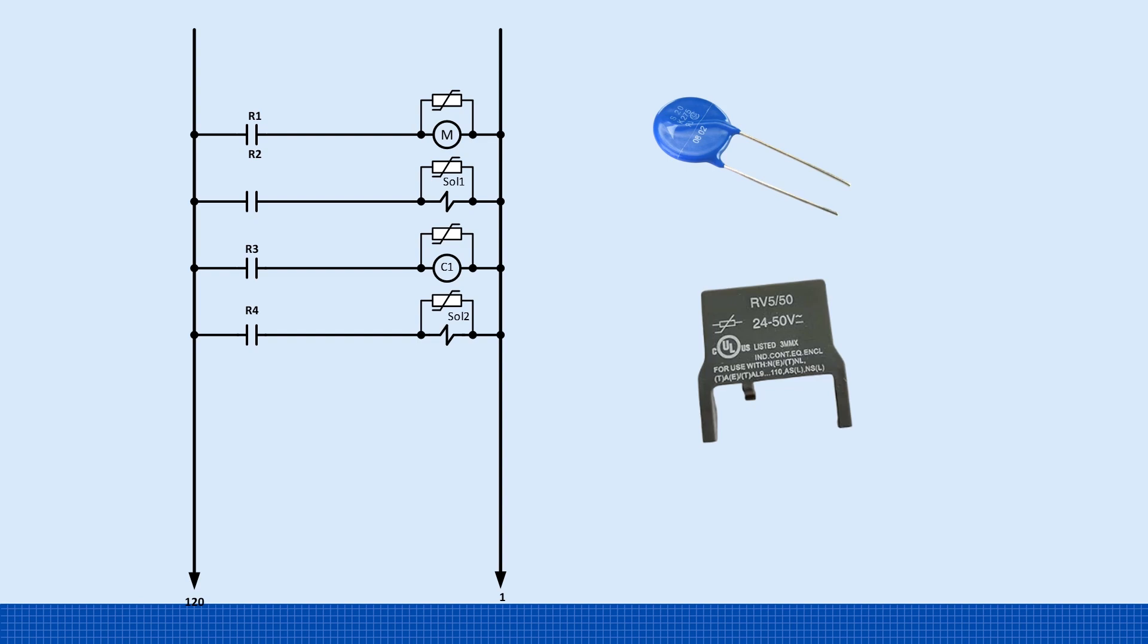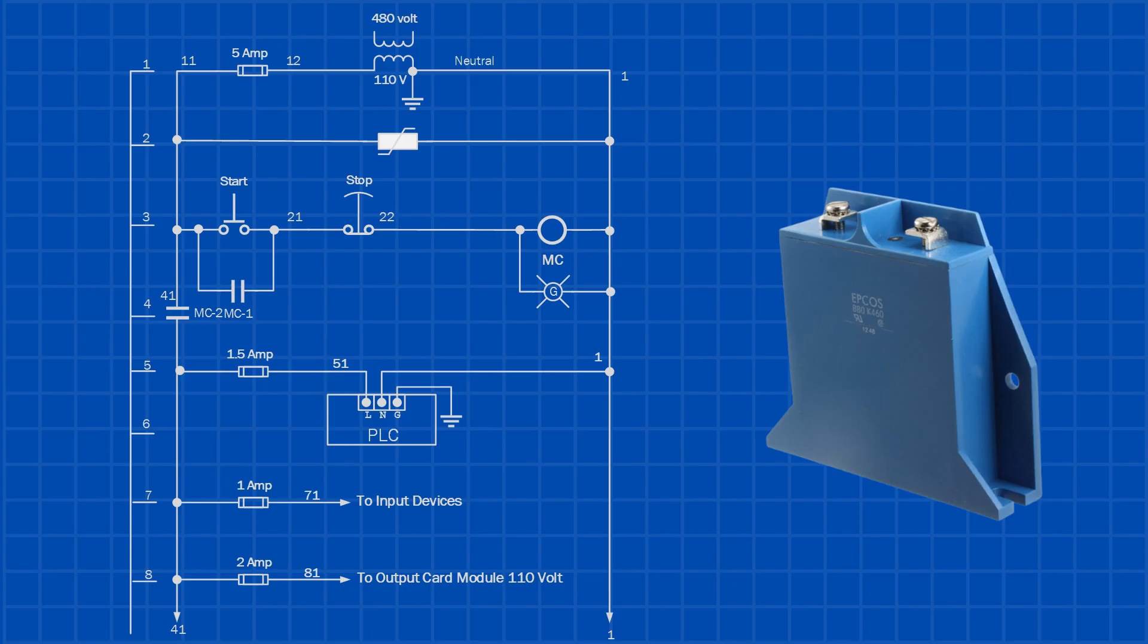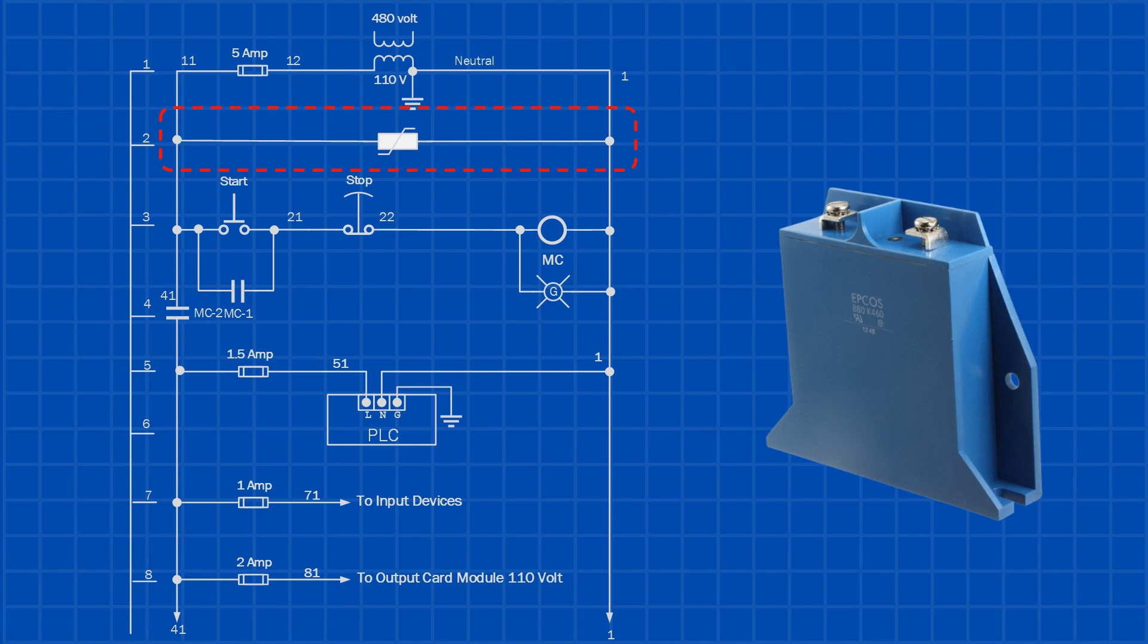First, install surge suppressors, such as snubber circuits or MOVs in parallel with each coil. These components absorb the energy released when the coil de-energizes, preventing it from damaging other parts of the system. Second, install a surge suppressor in the main control circuit, right after the control transformer. This provides system-wide protection. If the suppressor fails and shorts, the control fuse will blow, isolating the fault safely.